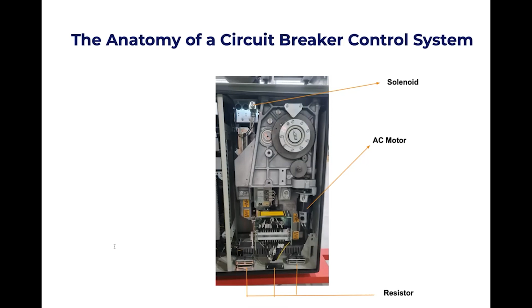in the control system for a circuit breaker, typically functioning to charge the stored energy in the operating mechanism of the circuit breaker. In some types of circuit breakers, this stored energy is used to trip or close the breaker contacts, and the charging motor is responsible for maintaining the stored energy level by continuously charging the mechanism.